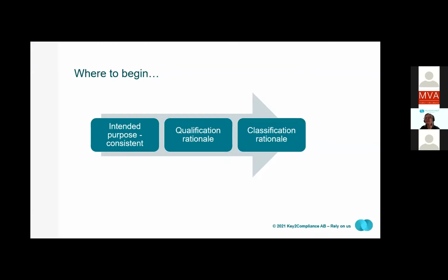When you start to update your technical documentation according to MDR, you will gain a lot of time by thoroughly going through your intended purpose and the classification before starting to update the rest of the documentation. First of all, you need to establish your intended purpose, since this will be the ground for your classification, and by all means, the remaining documentation, of course. Once you have decided about the intended purpose, you can then decide about the classification.